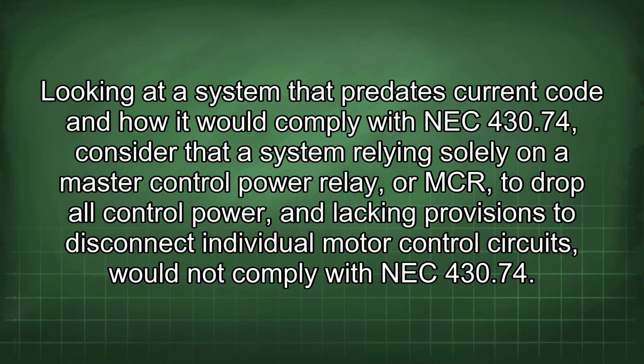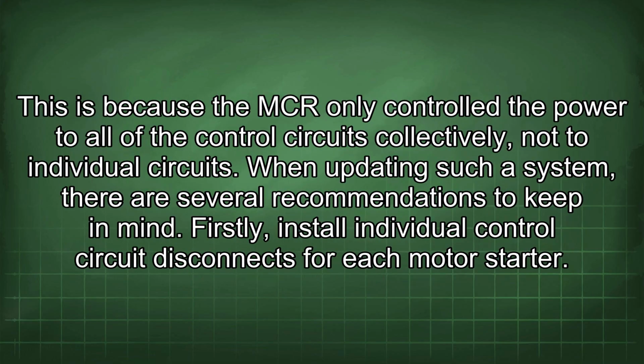Looking at a system that predates current code and how it would comply with NEC 430.74, consider that a system relying solely on a master control power relay, or MCR, to drop all control power and lacking provisions to disconnect individual motor control circuits would not comply with NEC 430.74. This is because the MCR only controlled the power to all of the control circuits collectively, not to individual circuits. When updating such a system, there are several recommendations to keep in mind.